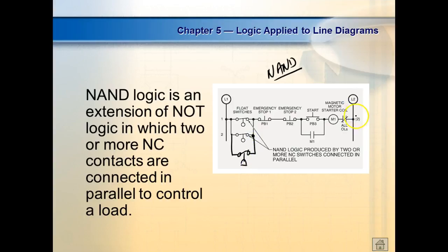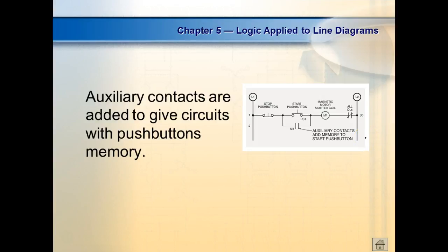Now look, every time in the book, if they have a connection, they put a what? A dot. So if you leave those dots off, what does that mean to me? So what am I going to do? I'm going to put like a -2 or something like that. Auxiliary contacts are added to give circuits with push buttons memory. So this guy right here has 2 auxiliary contacts. Where was that?